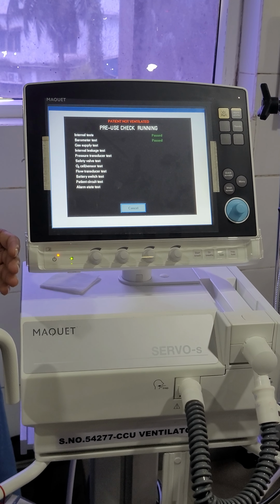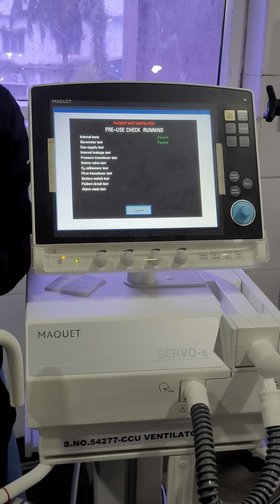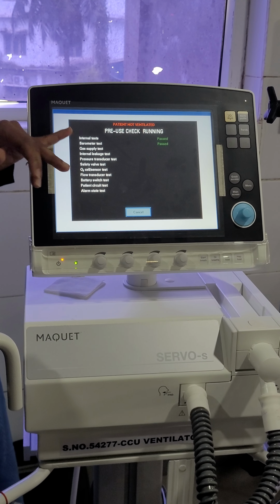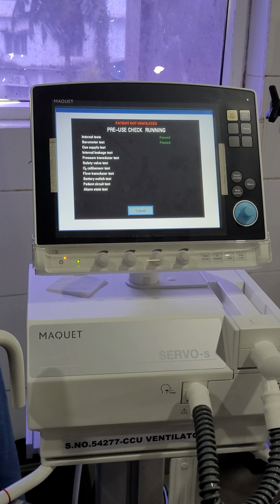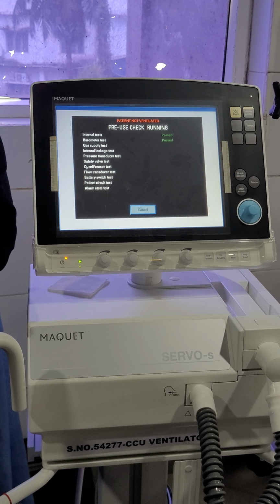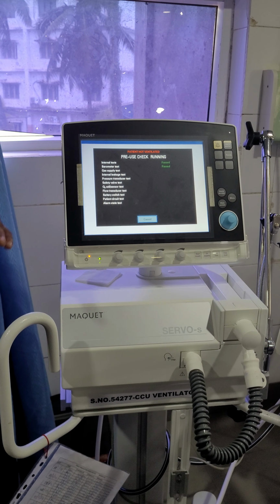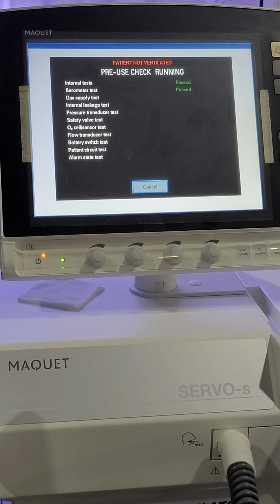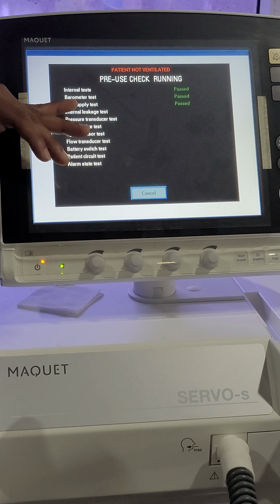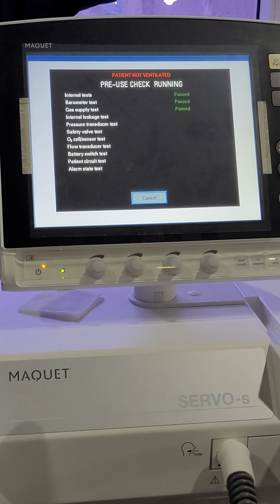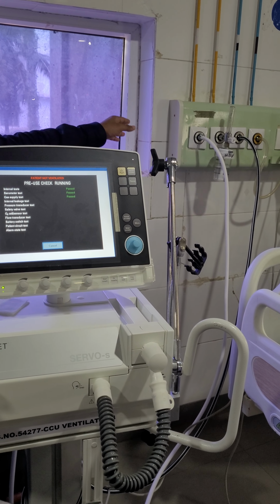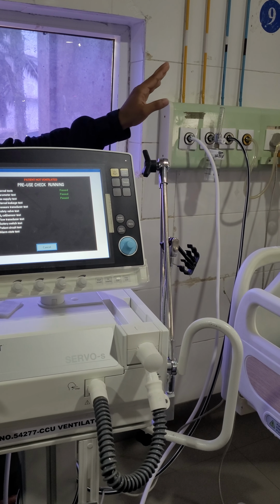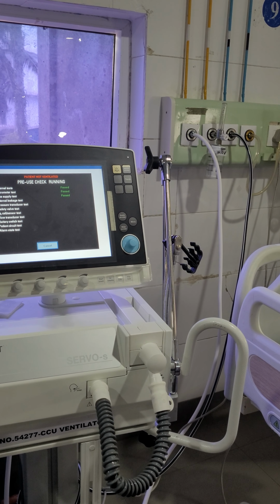Internal test: it is checking the alarms and the cables, whether they are working within normal limits or not. Barometric test: it is measuring the atmospheric pressure, ours is 760 mmHg at sea level. The ventilator makes sure that it can work in any part of the world. Gas supply test: how much oxygen and how much air is coming from the station outlet. It has to be more than 3.5 bar.